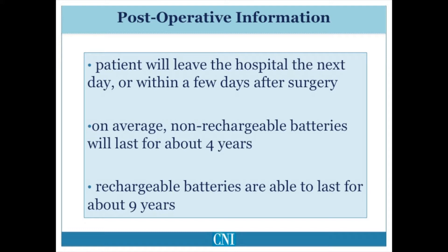Activating the stimulation and programming the specific parameters appropriate for chronic stimulation usually begins one or two weeks after electrode implantation, to allow swelling around the implanted electrodes to resolve first. The FDA-approved deep brain stimulation systems include rechargeable pulse generators or non-rechargeable pulse generators. The lifespan of non-rechargeable systems varies substantially from patient to patient depending on the current drain that occurs with the specific stimulation parameters required for an individual patient.